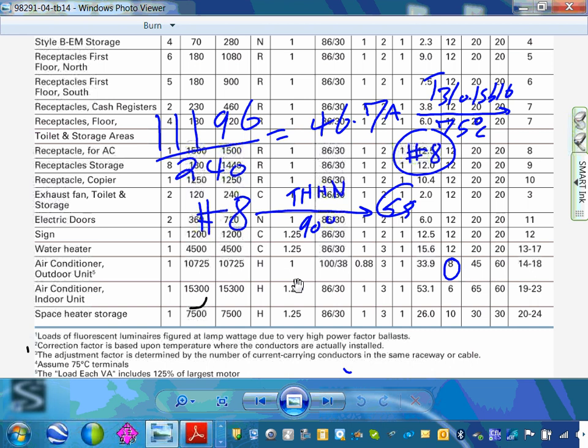You have 50? So is 50 under 75? Yeah. I bet that's what he used, that this was THW, because, yeah, it makes sense. Thank you. Everybody understand that? Good point. Because outdoor, that would be 75 degree. This then will be 50. What about the minimum allowable capacity?